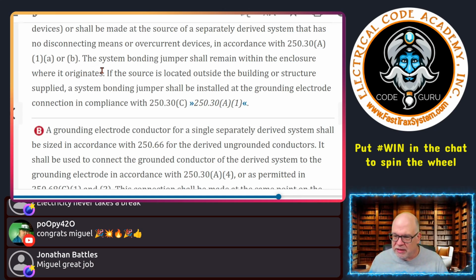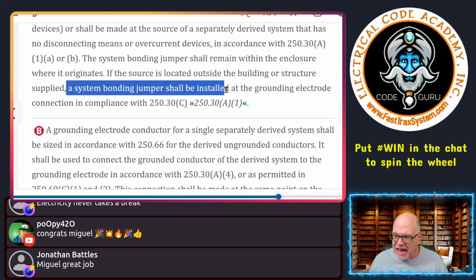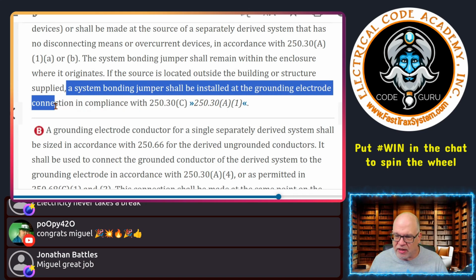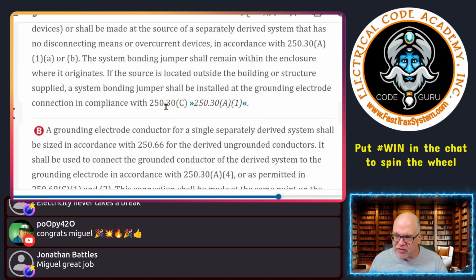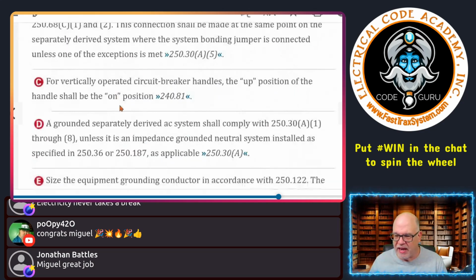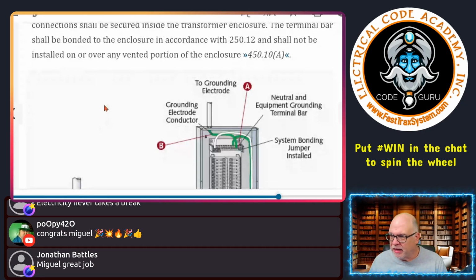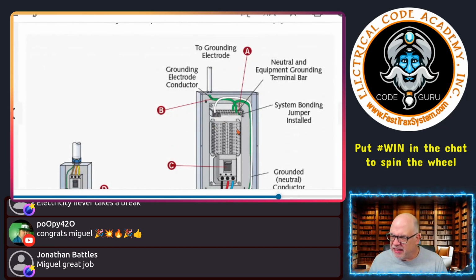Okay, so say it's located outside, and then it says a system bonding jumper shall be installed at the grounding electrode connection in accordance with 250.30C. Okay, so wherever we're installing that grounding electrode connection, that is where we're going to install the system bonding jumper. And you see it says A, and it calls out A right there. This just happens to be right there. That is the system bonding jumper installed right here.